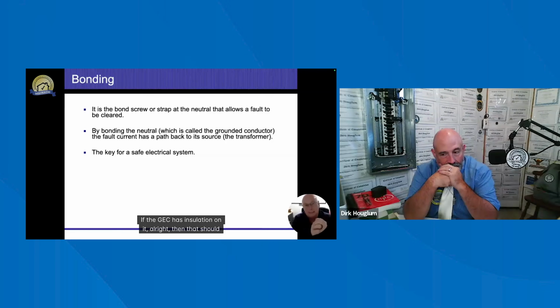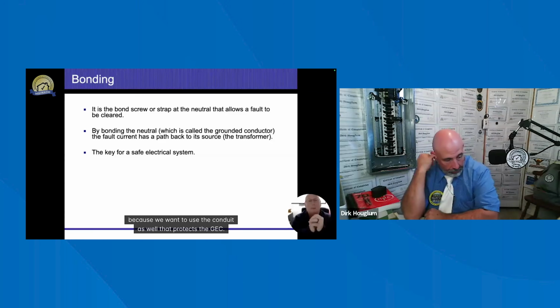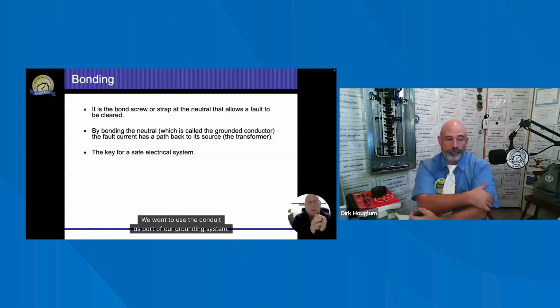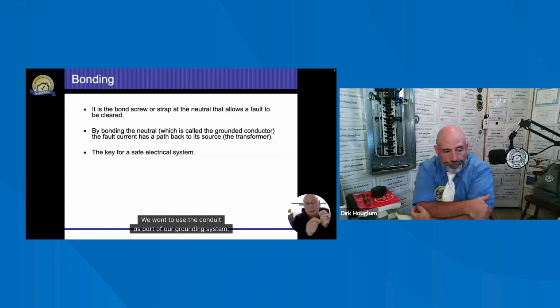If the GEC has insulation on it, all right, then that should have a mechanical connection because we want to use the conduit as well that protects the GEC. We want to use the conduit as part of our grounding system. So we need to have a mechanical connection pretty much at both ends to the conduit.